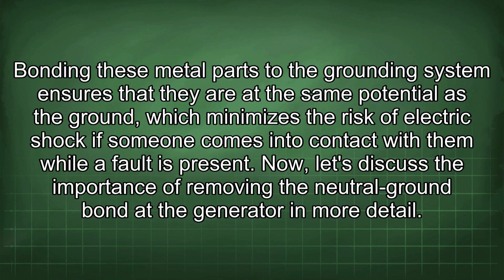Bonding these metal parts to the grounding system ensures that they are at the same potential as the ground, which minimizes the risk of electric shock if someone comes into contact with them while a fault is present. Now, let's discuss the importance of removing the neutral ground bond at the generator in more detail.